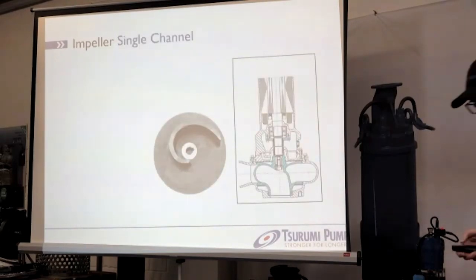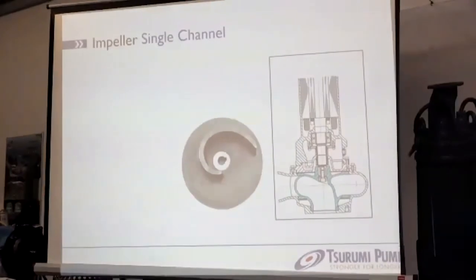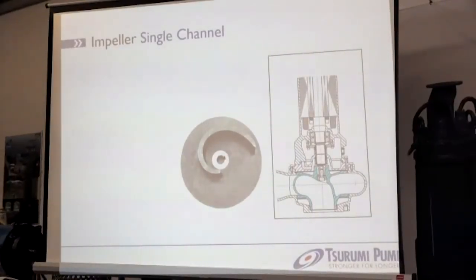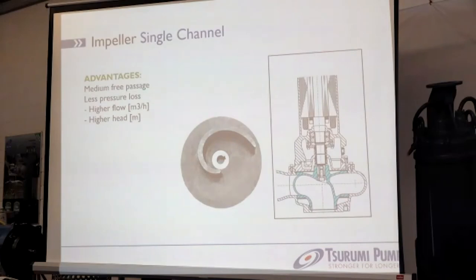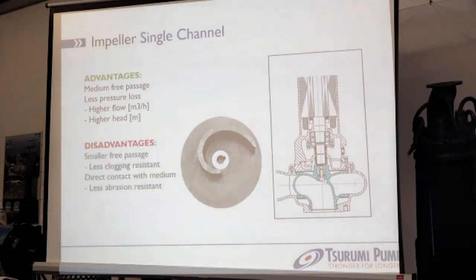The next impeller type is the single channel impeller — and the arguments for single and double channel impellers are fairly the same. Advantages of a single channel impeller: medium free passage, which you can see directly on the drawing — smaller than the vortex impeller but still bigger than other impeller forms we will discuss later. There is less pressure loss, resulting in higher flow and higher head.